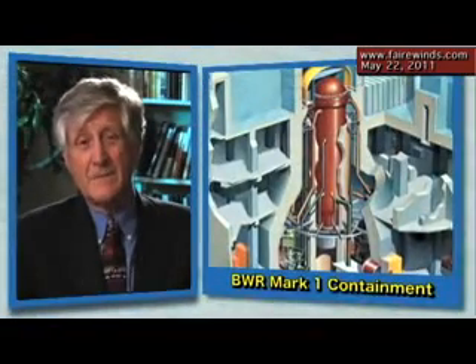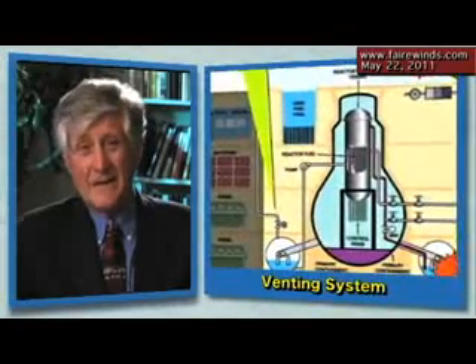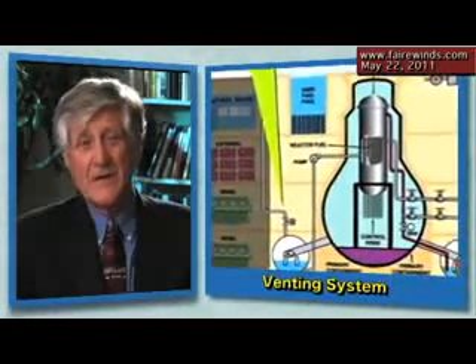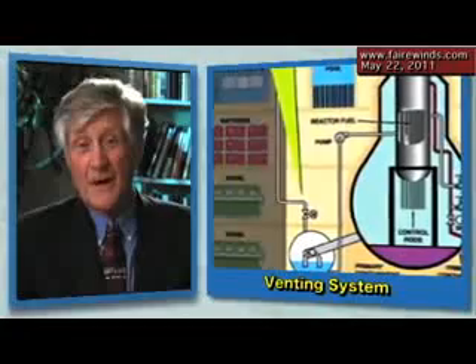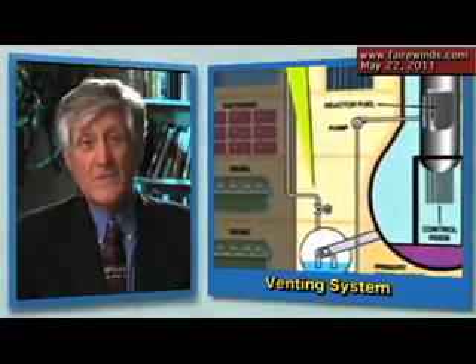Today I wanted to talk about the lessons that can be learned worldwide for the operating nuclear reactors that are already done and in use, not under construction. The first and most obvious thing is the containment. Containments were made to contain radioactivity. The vents you hear about and how they failed were an add-on. Back in the 70s and 80s when these plants were designed, they weren't designed to have a vent. The pressurized water reactors around the world don't have a vent even now. So these containment vents were a band-aid fix to a problem that was identified after they were built.